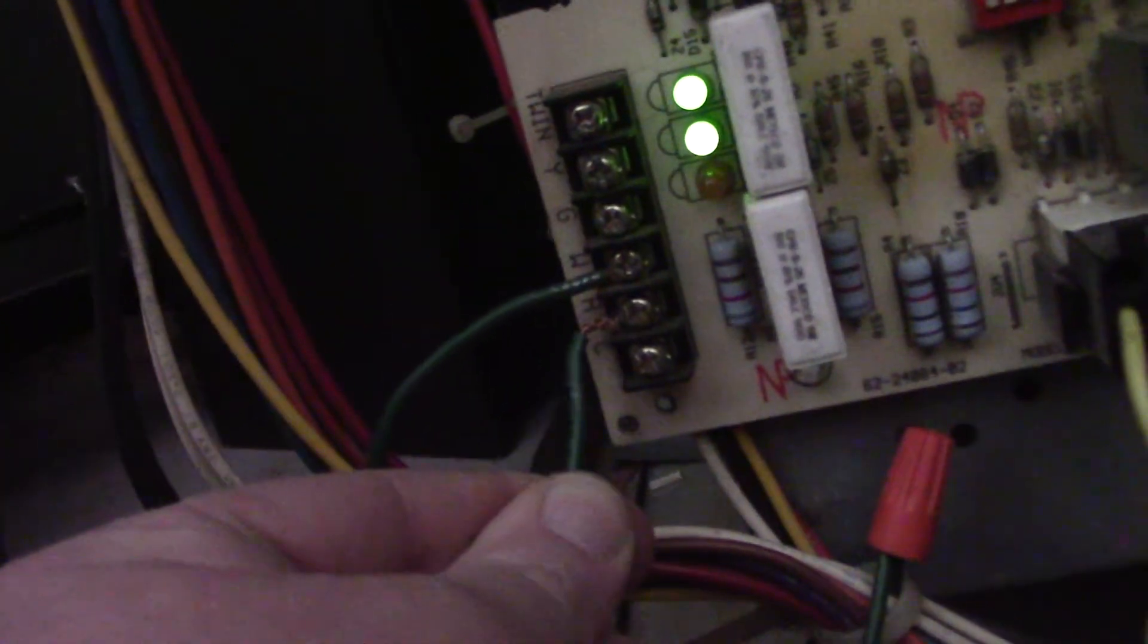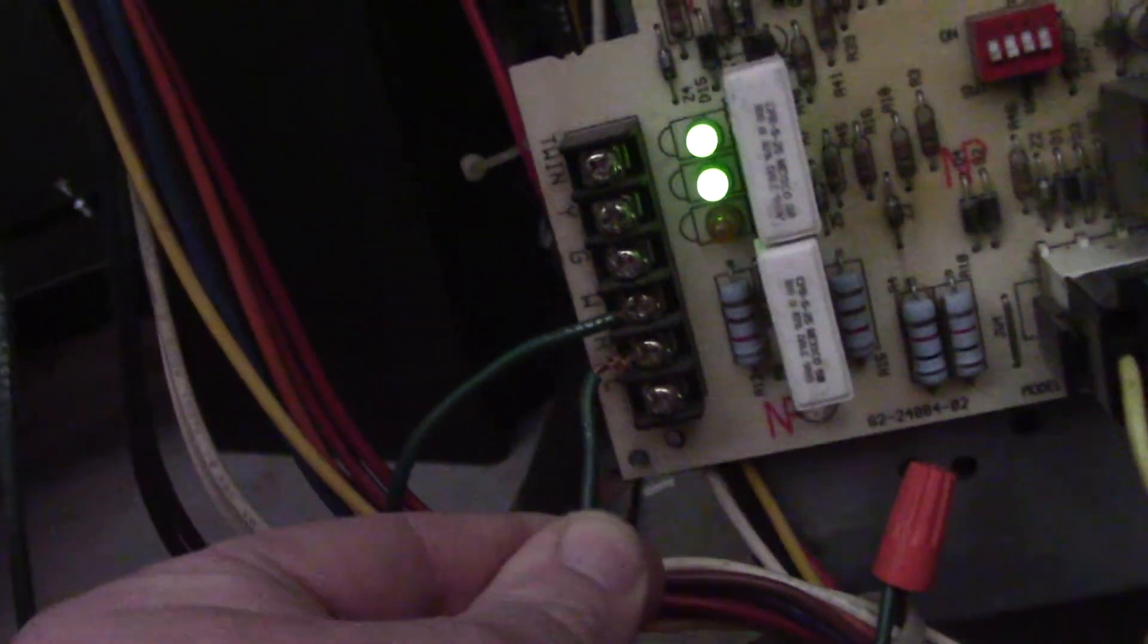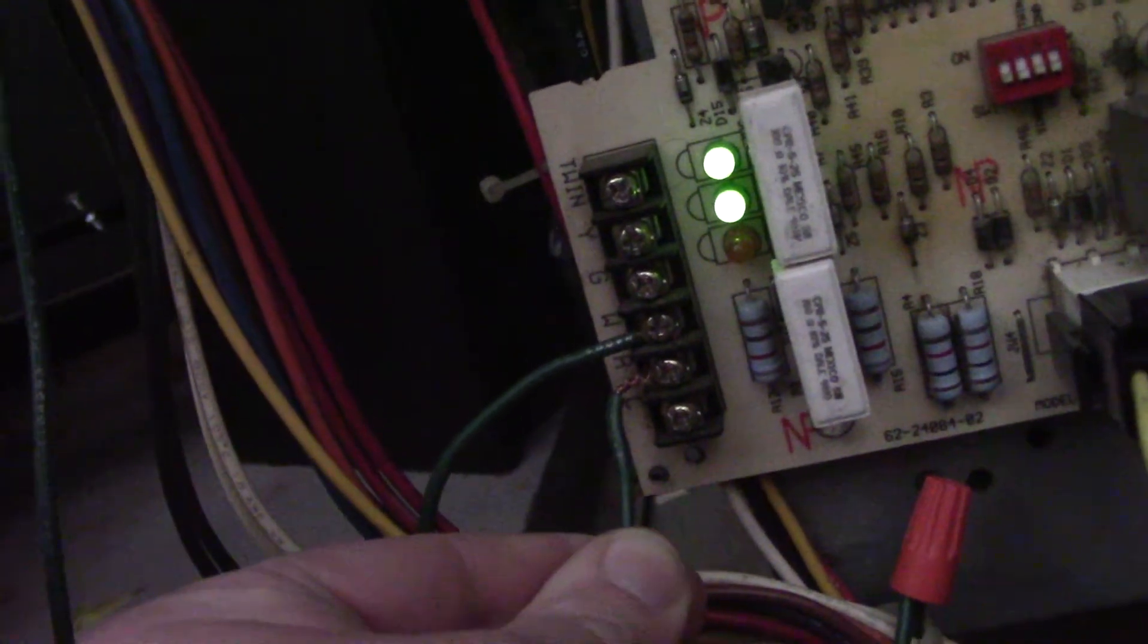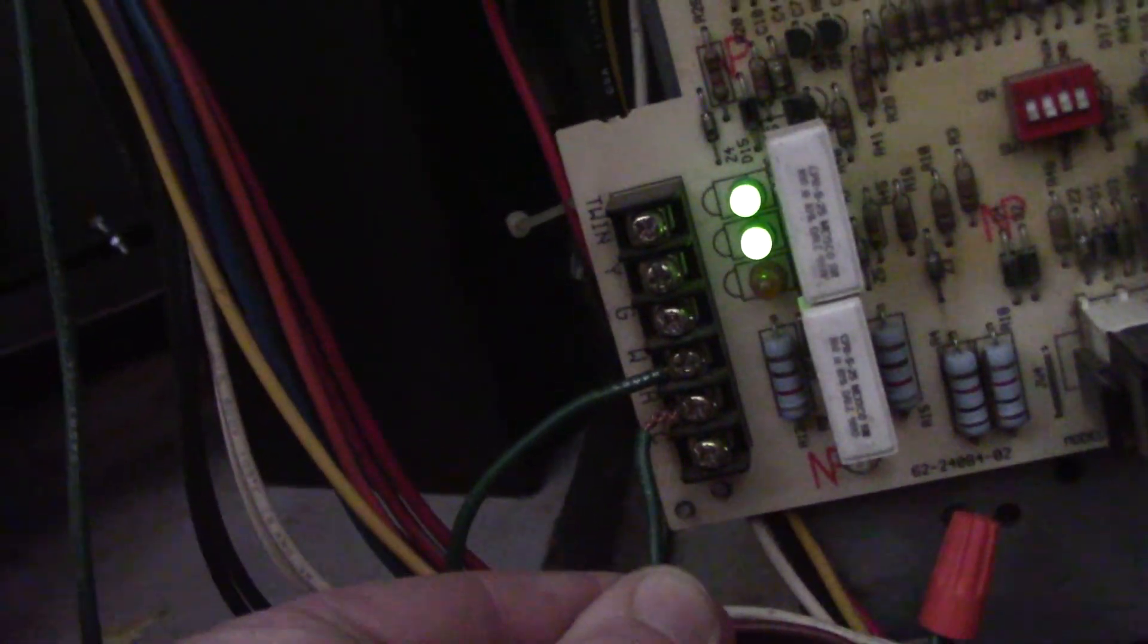If you want to test real quick, no heat, no diagnostic code, take a jumper wire W to R. Oh, it's coming alive, it wants to work now. Congratulations, you have proved that the furnace board is okay. You have a problem with your thermostat wire.